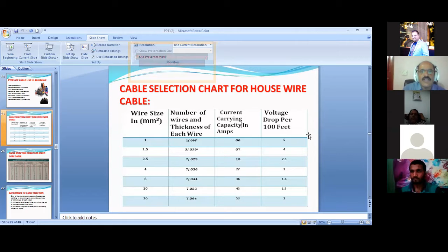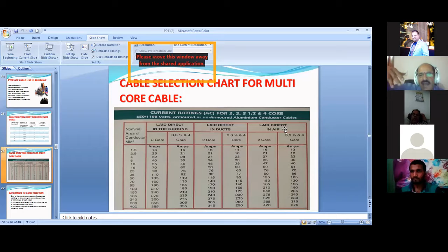This is the selection table of multi-core cables, the 3.5 and 4 core cables. When laid directly in the ground, these are the current ratings. When it is laid inside ducts, this is the current rating. When it is laid directly in the air, when it is hanging in the air, this is the current rating. See, there is a drop in the current ratings when it is laid in different ways.